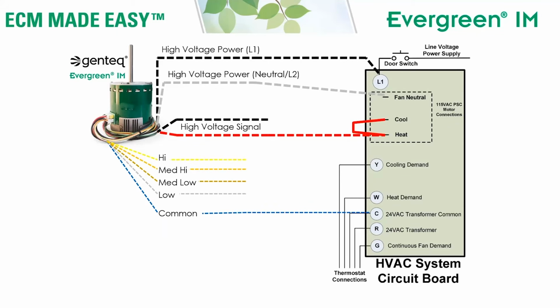We're going to connect whatever speed we want for heat to the thermostat heat demand, which is usually designated with a W. And we're going to connect whatever speed we want for cooling to the thermostat cooling demand, which is usually designated with a Y. Now I've put the yellow wire on Y and the white wire on W, but you could use that as a starting point.